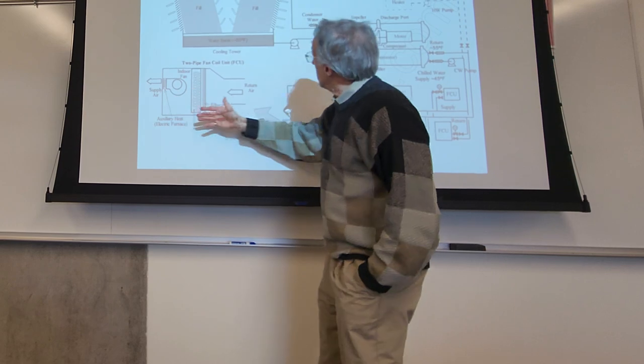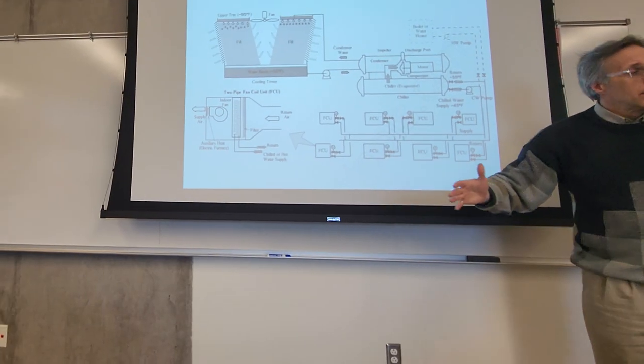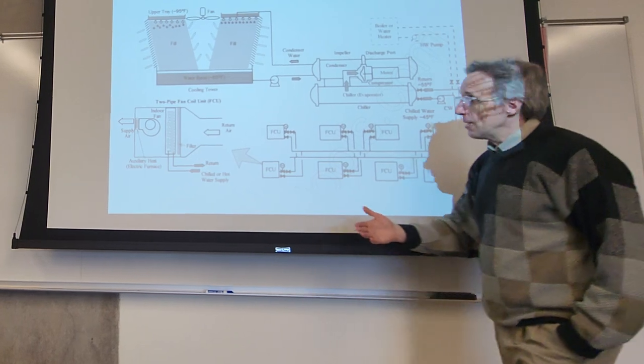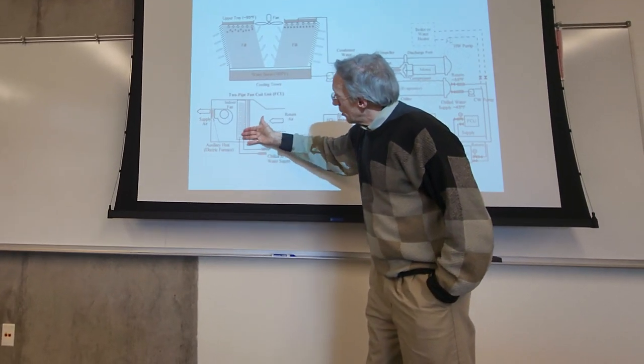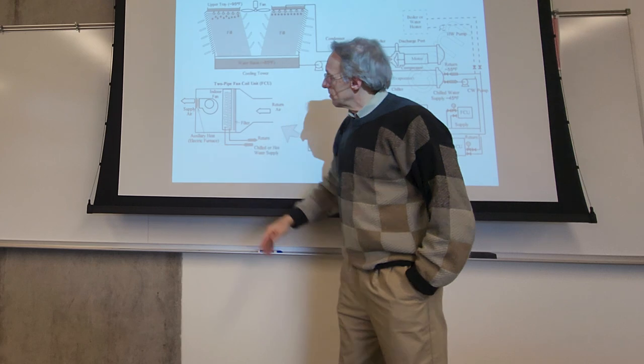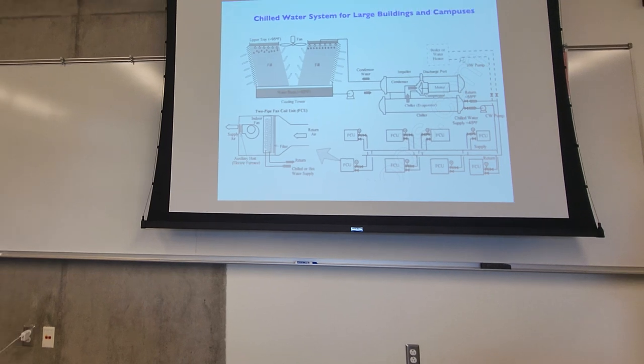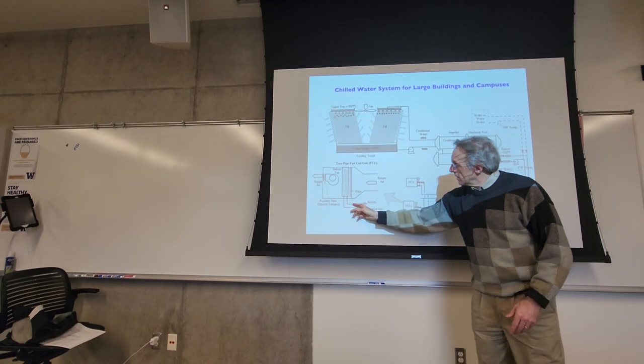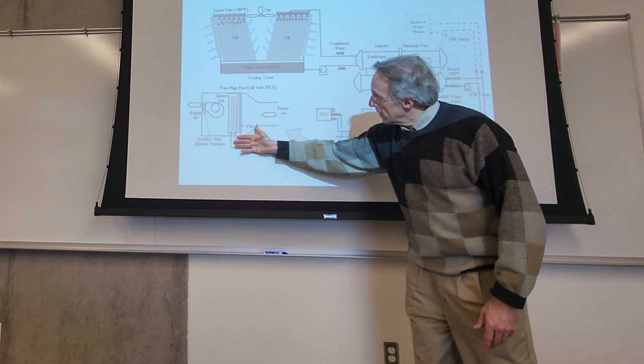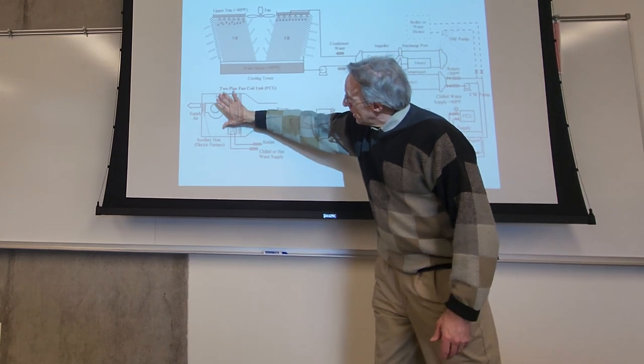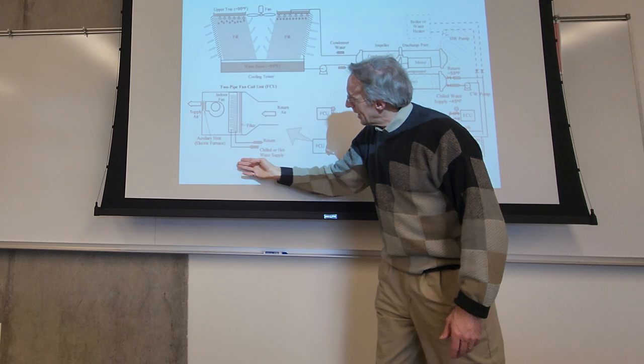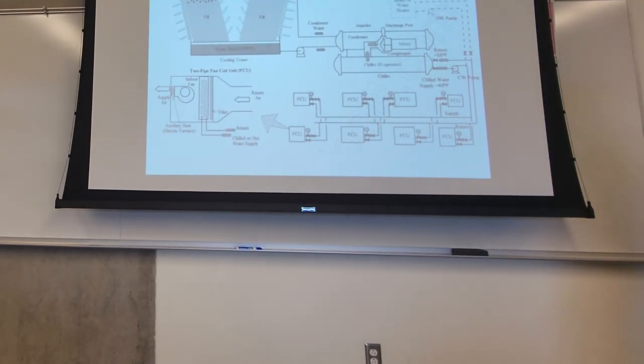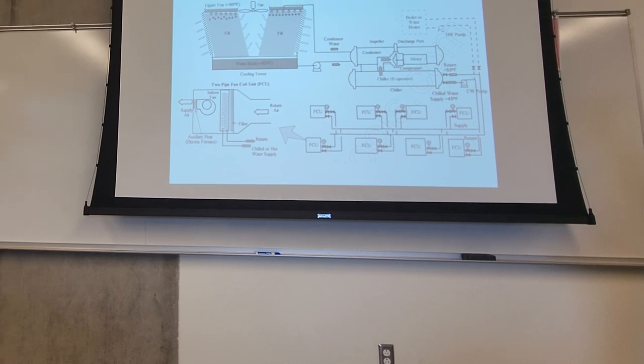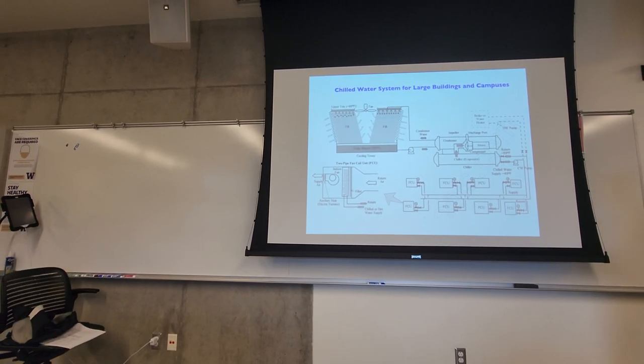So a lot of buildings will have a boiler to make hot water. So in the wintertime, you can shut that off and you have hot water there, and that makes warm air. And then a lot of buildings nowadays have both. They have systems that are called four-pipe systems. This is a two-pipe system. A four-pipe system, you can have both. You would have another coil here that would be connected to your source of hot water, which would normally be a boiler of some kind, or it could be a heat pump as well.